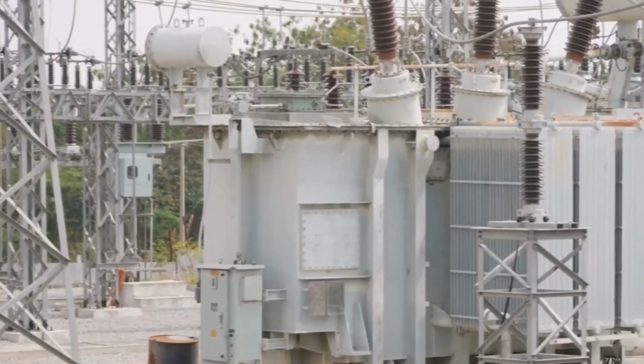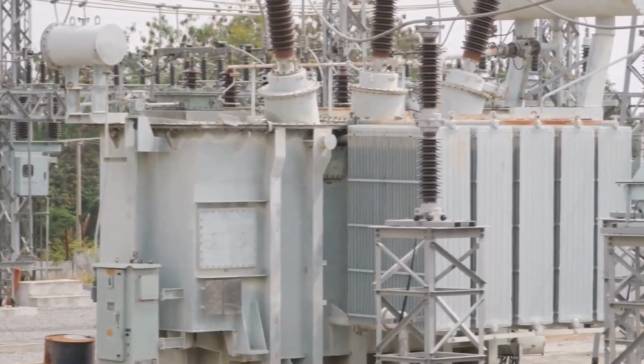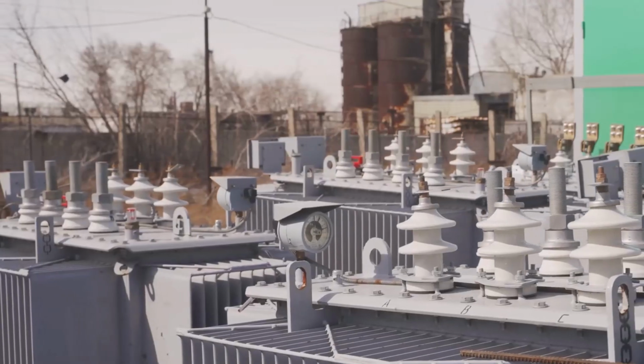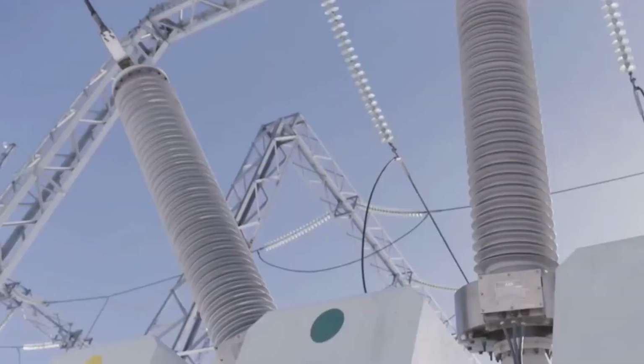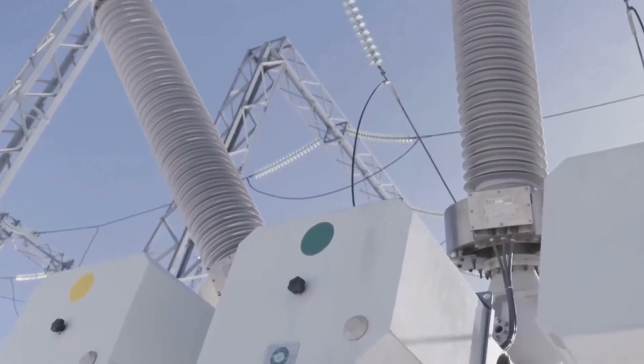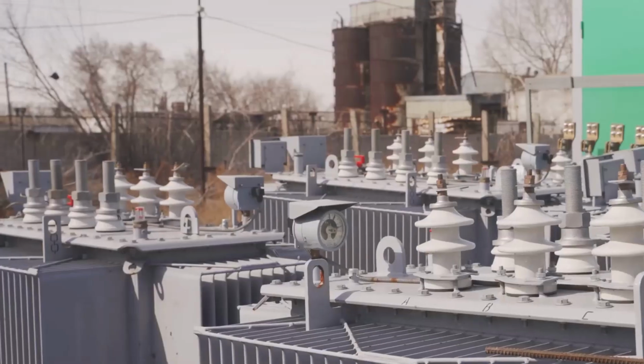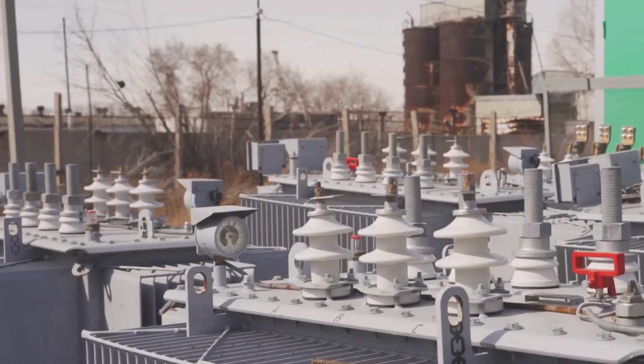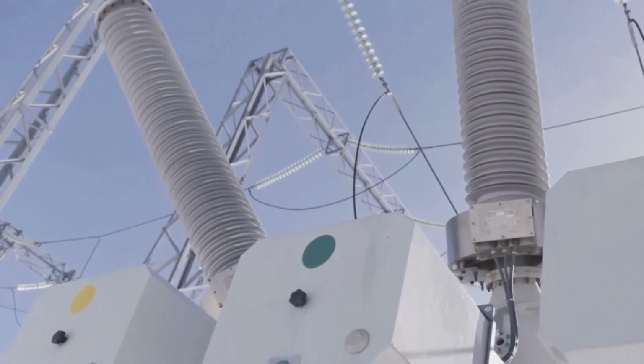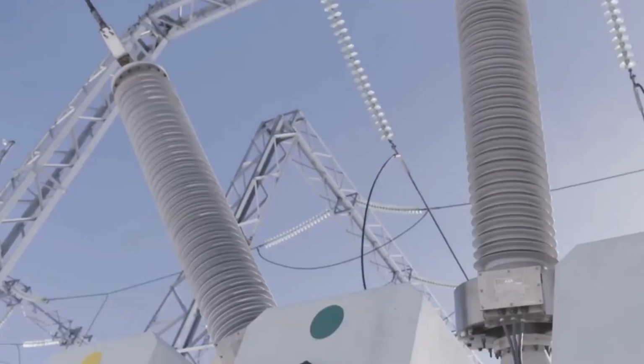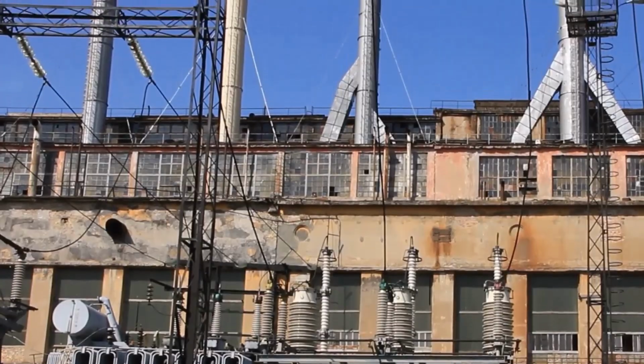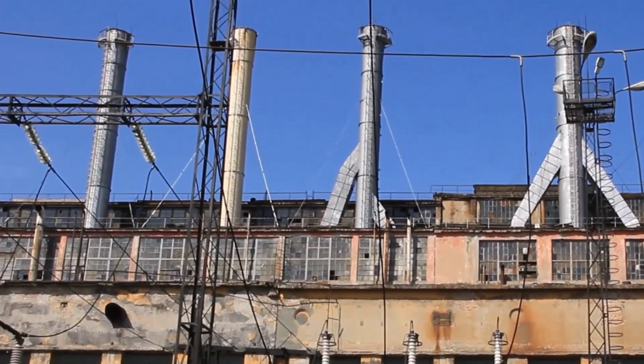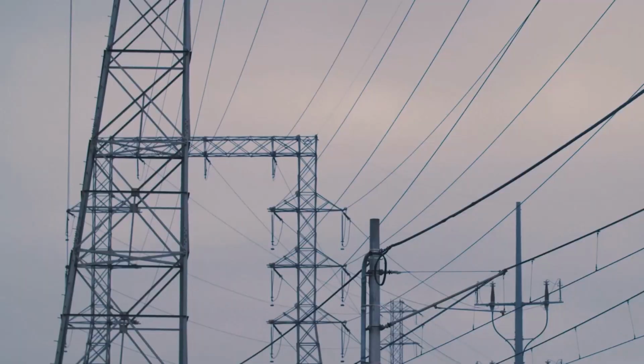A third very common place to find a delta setup is inside the windings of a transformer itself. Transformers often have different connection types on their primary or input and secondary or output sides. A very common configuration is a delta Y transformer. In this setup, the high-voltage primary side is connected in delta to handle the incoming transmission voltage. The secondary side is then connected in a different configuration called a Y or star, which does have a neutral point. This allows the transformer to supply power to both three-phase industrial loads and single-phase residential loads, giving us the best of both worlds.